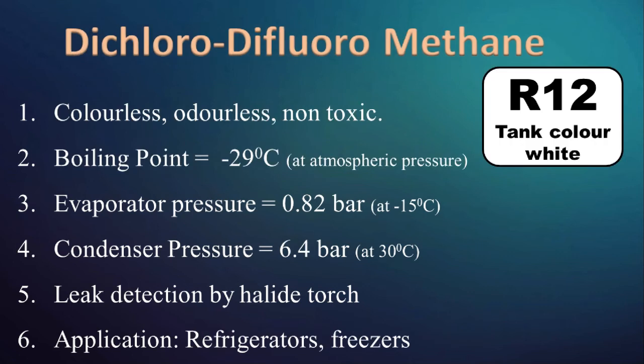R12, Dichlorodifluoromethane, is colorless, odorless, non-toxic, non-corrosive, non-flammable, and was very popular in the HVAC industry. Boiling point of R12 is minus 29 degree Celsius, with evaporator pressure of 0.82 bar and condenser pressure of 6.4 bar. It has a lower latent heat of vaporization, which helps to use less sensitive regulating mechanisms in the system. R12 leak detection can be done by Halide torch. Its cylinder color is white. Applications of R12 are in refrigerators, freezers, and AC systems with rotary compressors.